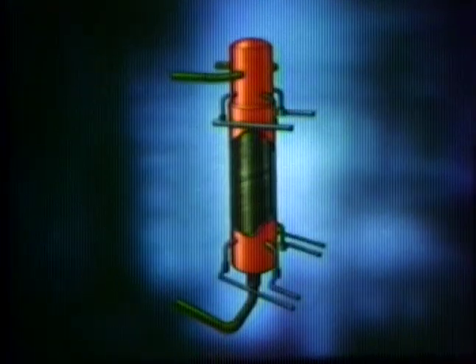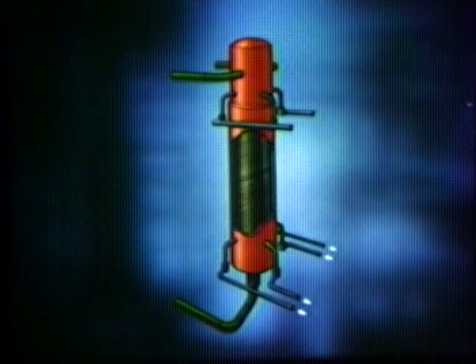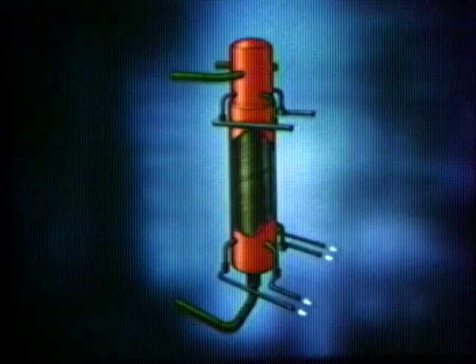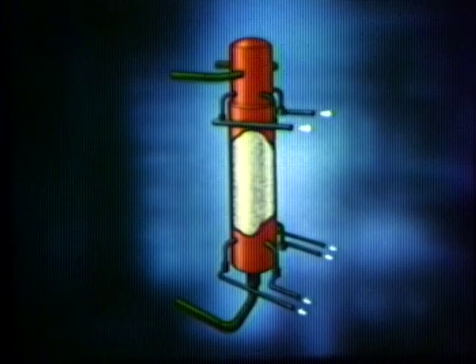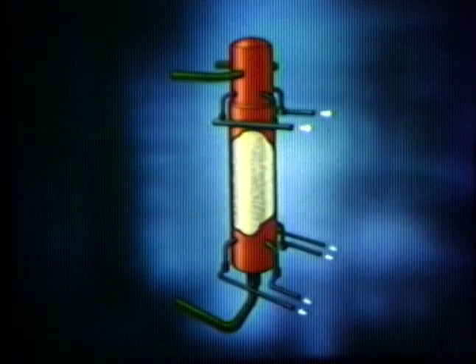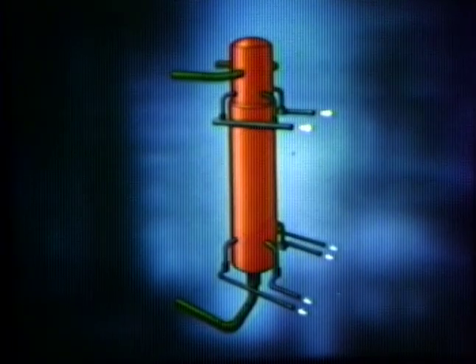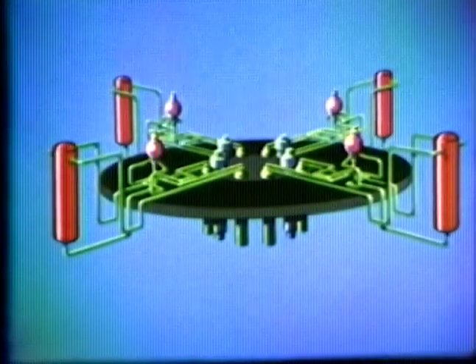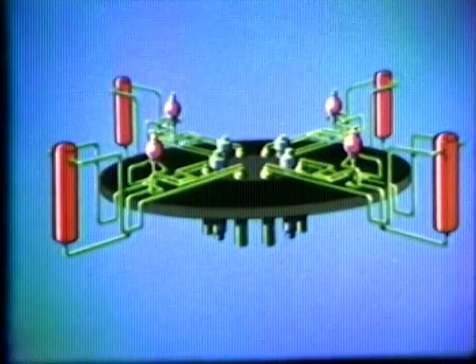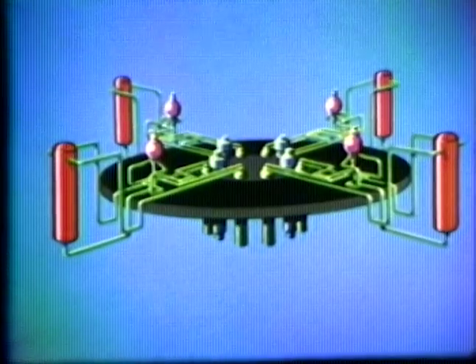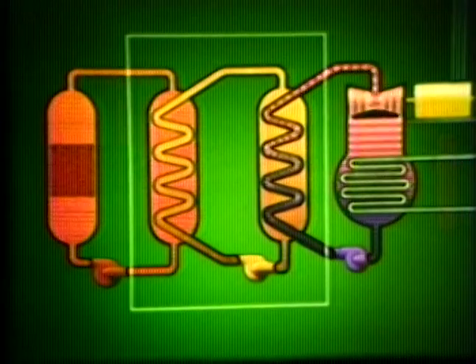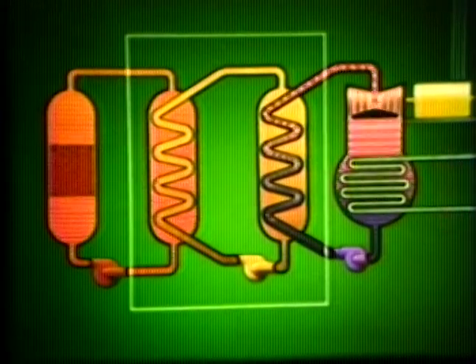Feed water enters at the bottom of the steam generator, heats up, and vaporizes in the tubes immersed in the secondary sodium, then leaves in the form of steam at a pressure of over 180 bars and a temperature of 490 degrees centigrade. This is the function of the 4 steam generators at the end of the 4 secondary loops, constituting the secondary or intermediate sodium system.